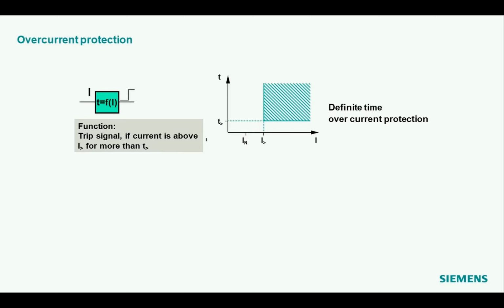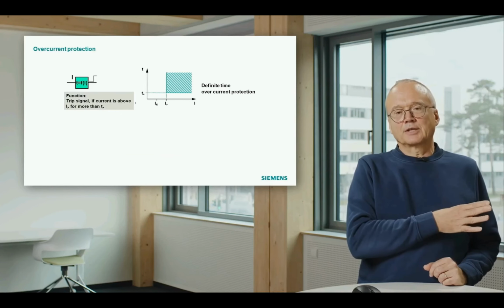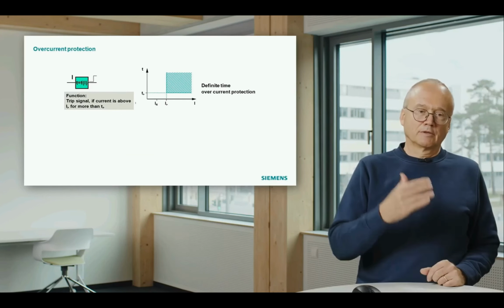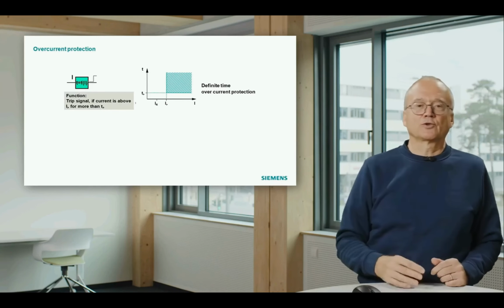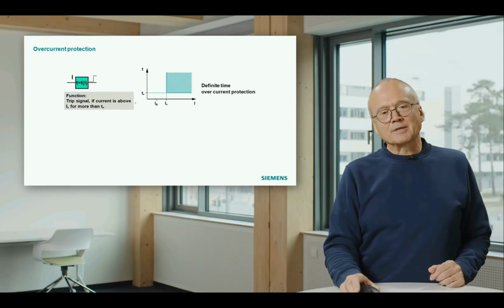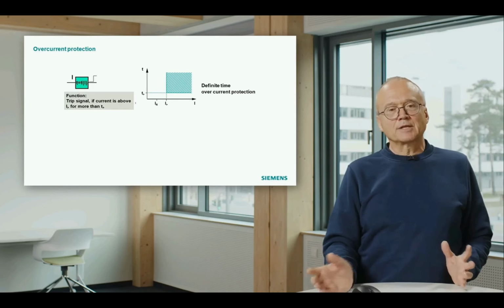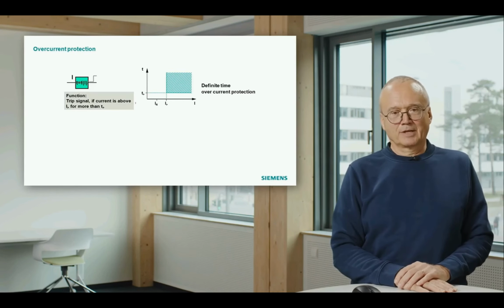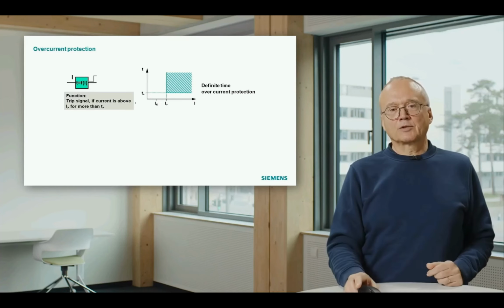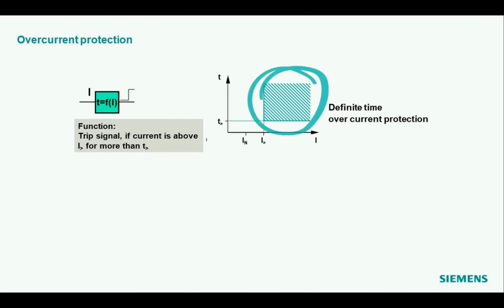That means this characteristic has basically 2 setting values. One is the current setting and one is the timer setting. The current setting is derived from the considerations I did on the previous slide: above maximum load current plus a certain security margin. The timer setting comes from the selectivity considerations we will discuss later on. This type of protection with this defined time as soon as we are above a limit is called definite time overcurrent protection.